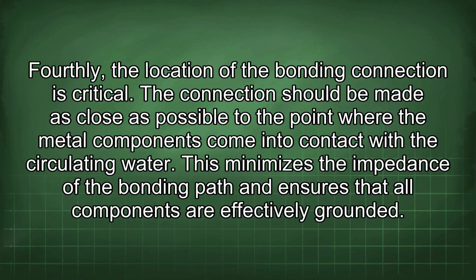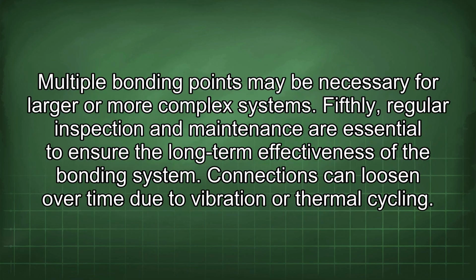Fourthly, the location of the bonding connection is critical. The connection should be made as close as possible to the point where the metal components come into contact with the circulating water. This minimizes the impedance of the bonding path and ensures that all components are effectively grounded. Multiple bonding points may be necessary for larger or more complex systems.